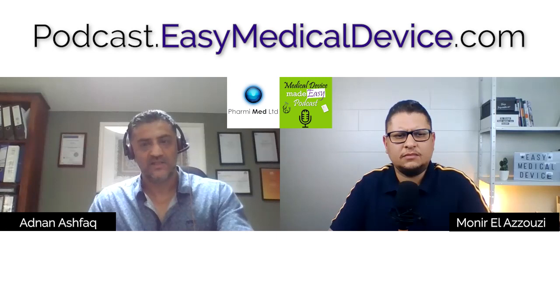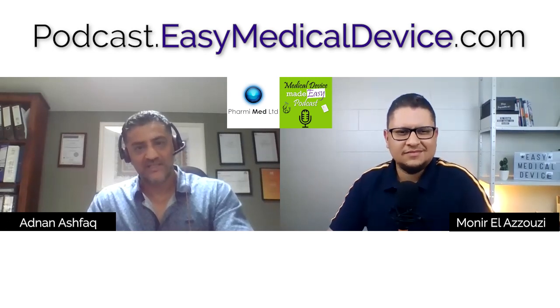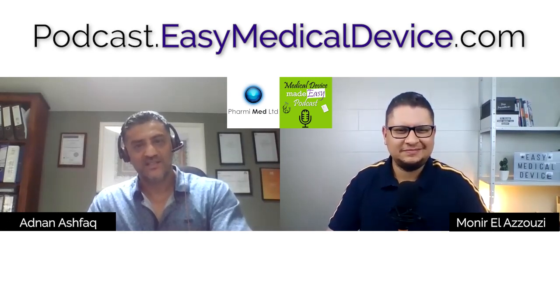And then when it comes to complaints and feedback, or even change, for example, if you make any change to the software, how do you document the change? One thing that we know for sure is that software is not the same as any other medical device like hardware, where you're having patches and releases on a very regular basis. So how do you manage the changes for this? Are you making a change control or a change for the design every time? Well, of course, this is not practical. So this is why you have to have an approach.